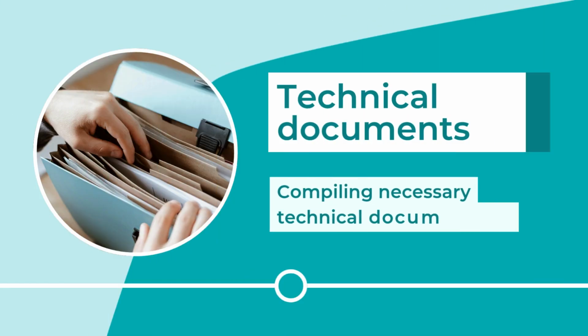During design and development, the device must comply with every applicable general safety and performance requirement in Annex I. Verification tests, risk control evidence, usability studies, and design outputs are compiled into the technical documentation structure defined in Annexes II and III.